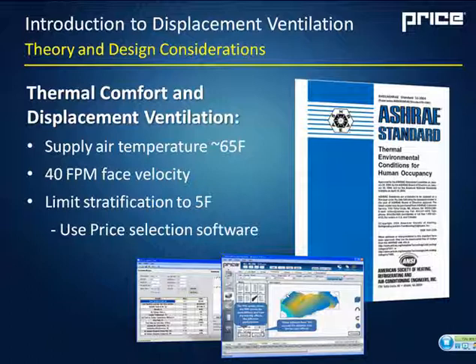And the final point out of the ASHRAE standard 55 is that we want to limit stratification to 5 degrees head to foot for a stratified system. That means the temperature difference between your head and your feet should not exceed 5 degrees, and that's simply because ASHRAE feels that once it exceeds 5 degrees, people are going to start to feel that their feet are cooler than their head, and they're going to start to feel uncomfortable. There are obviously calculation methods for trying to calculate this in a system. We actually have software that can help you predict this head-to-foot temperature, and also help you predict the supply temperatures and supply volumes that will help you stay within these guidelines.